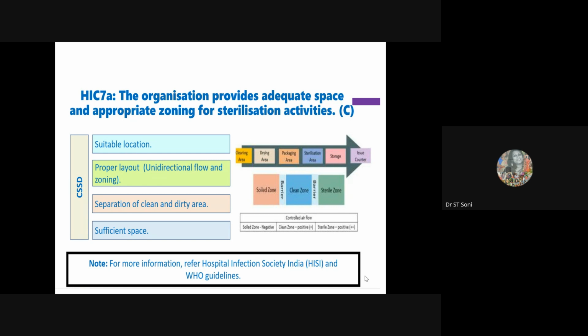There is a concept of zoning over here. So what happens if you are designing a central sterile supply department? First and foremost, if it is not decentralized, the used instrument will come from the operation theater, and that is a dirty area, there it will come for cleaning. There you clean it properly, put it in enzyme cleaner, put it in the washer disinfector, and scrub it appropriately, and wash it properly so that all blood, body fluid, and all organic material has gone, and then it goes to the drying area. Then it comes to a clean area where, after drying, you will pack it, and then it will be put into the machine.